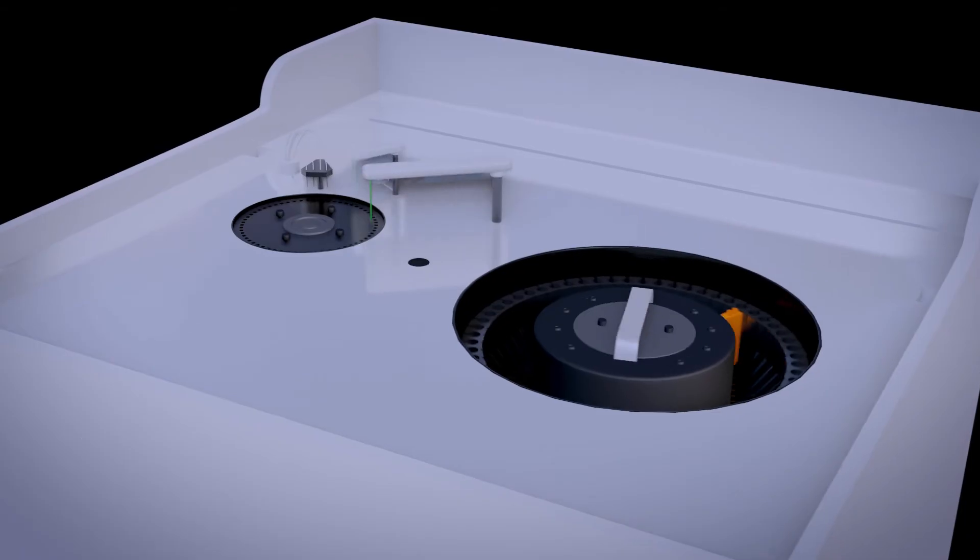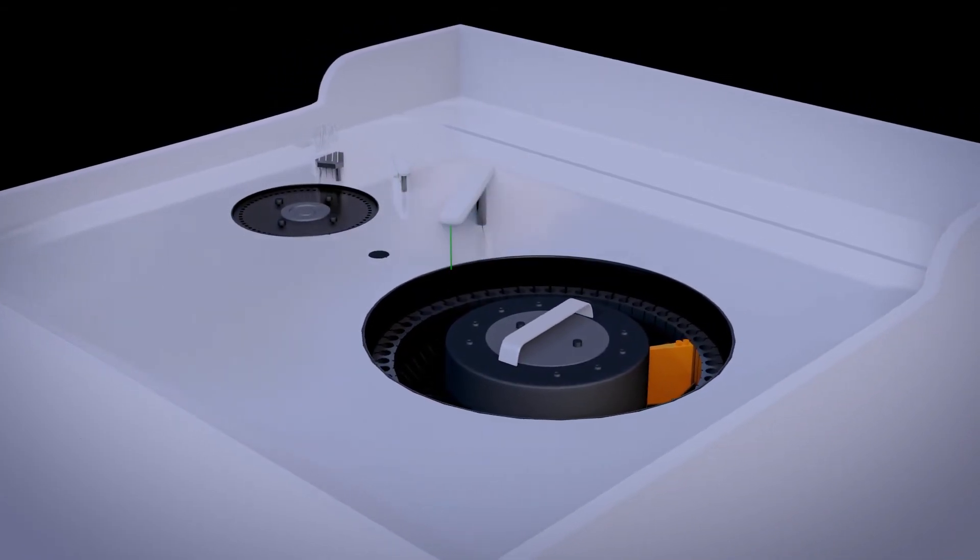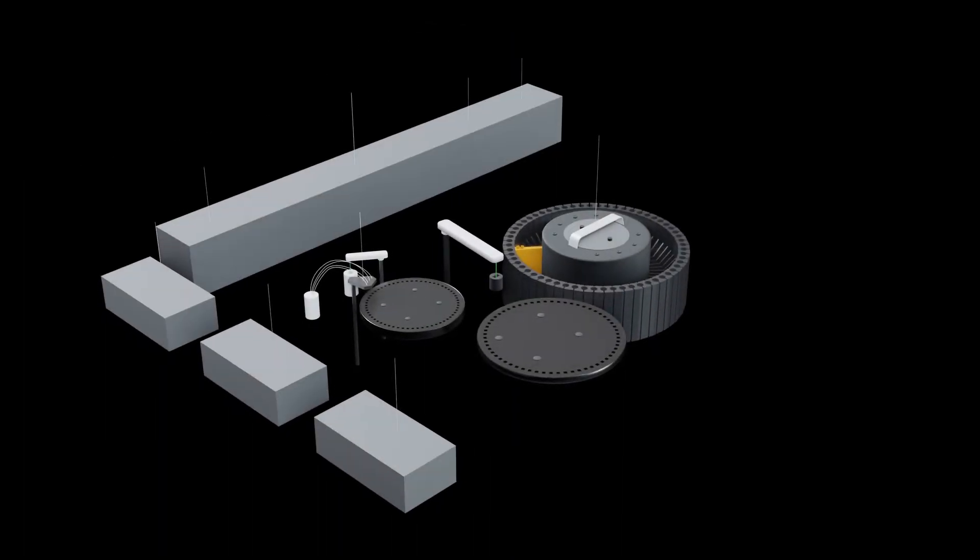As the probe movement into the sample cup was slow, the volume aspirated varied somewhat with the depth to which this was filled. The transit time between reservoir and sample is short.